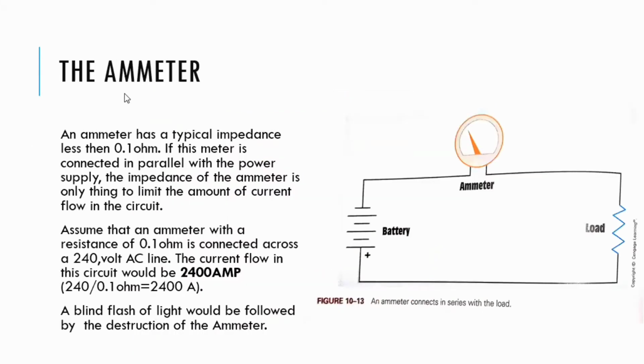The ammeter. The ammeter has a typical impedance, meaning resistance, load, resistance, capacitance and inductance, of less than 0.1 ohm. If this meter is connected in parallel with the power supply, this is very dangerous. The impedance of the meter is the only thing to limit the amount of current flow in the circuit.